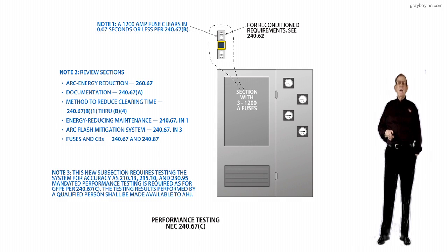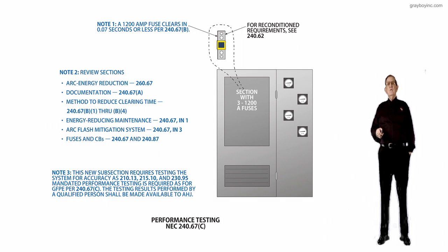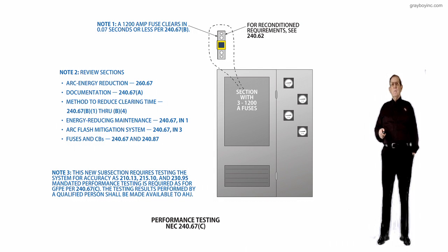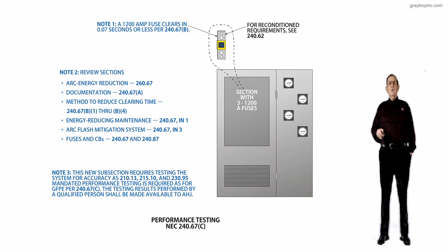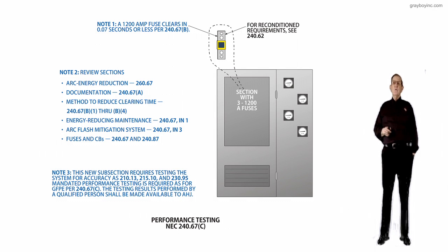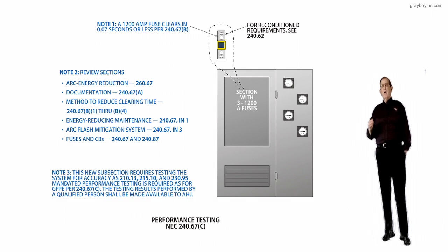And then I'd like to remind you in Note 3 that this new subsection requires testing the system for accuracy, to make sure that it's either branch circuit 210.13, feeder 215.10, or service 230.95. Performance testing is required for ground fault protection of equipment per 240.67(C), and the testing results performed by a qualified person shall be made available to the authority having jurisdiction of the state, county, or city involved.